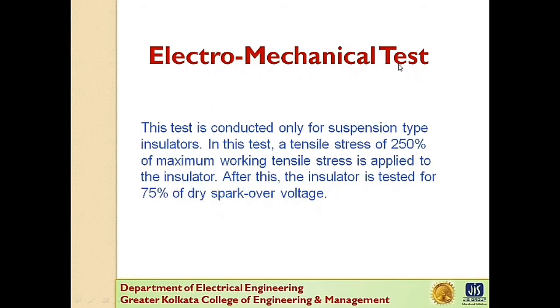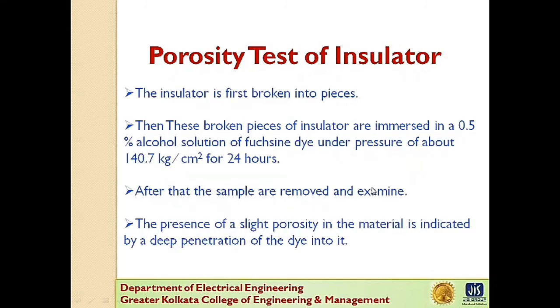Next one, electromechanical test. This test is conducted only for suspension type insulator. In this test, a tensile stress of 250% of maximum working tensile stress is applied to the insulator. After this, the insulator is tested for 75% of dry spark over voltage.